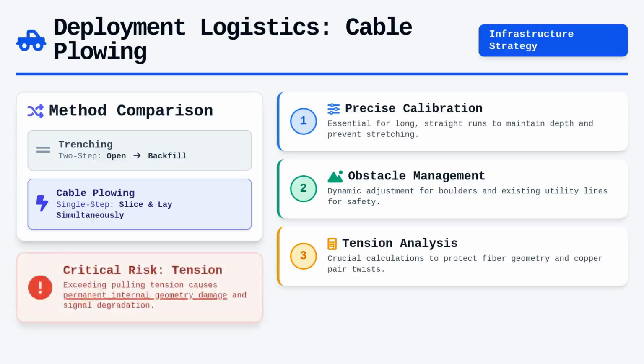Calculations for pulling tension are paramount here, as exceeding these limits can permanently damage the internal geometry of optical fibers or the twist characteristics of copper pairs, leading to intermittent signal degradation that may not immediately manifest as a total outage.